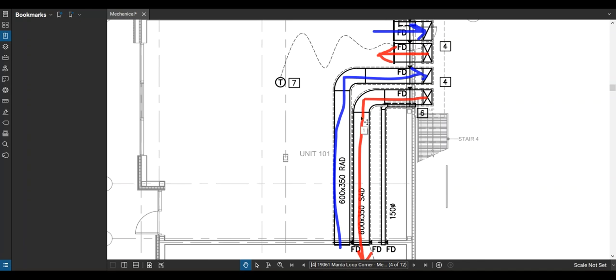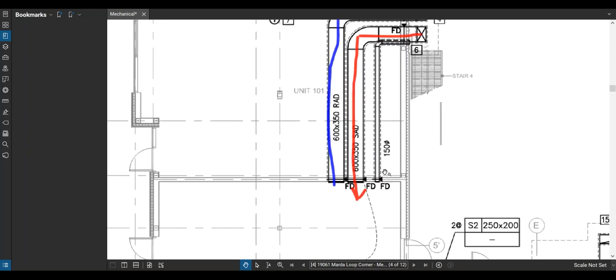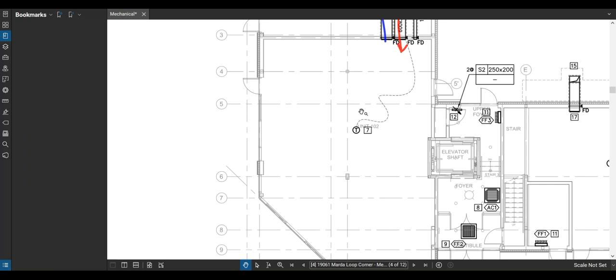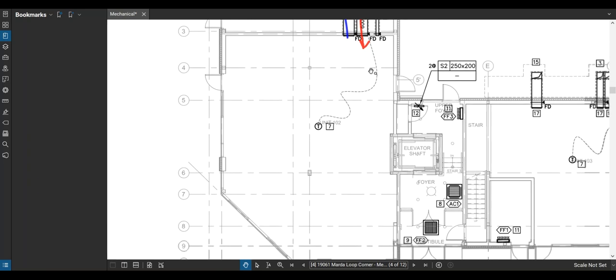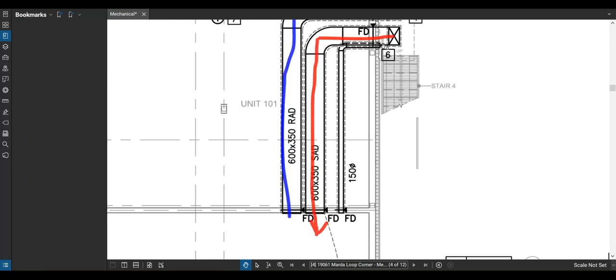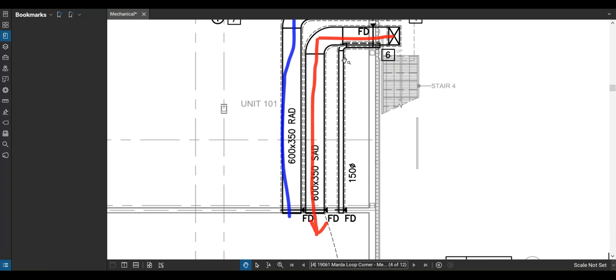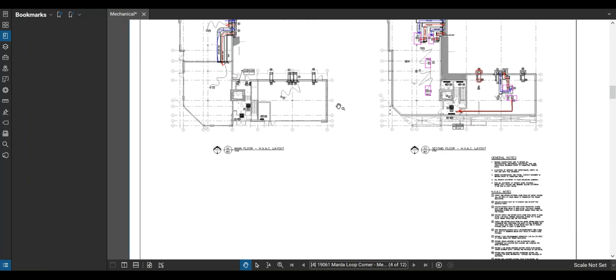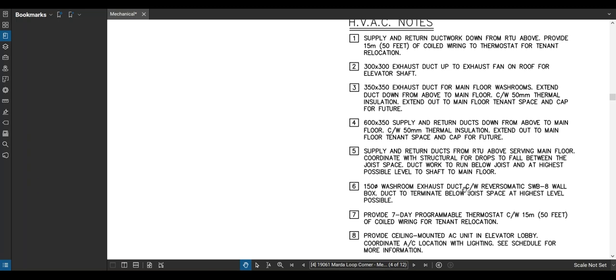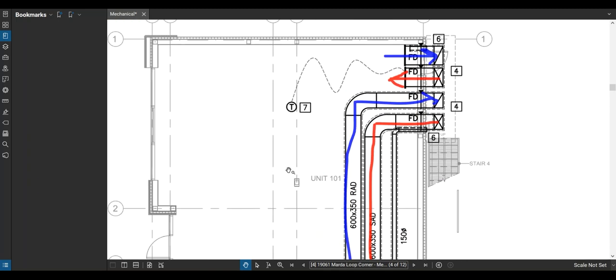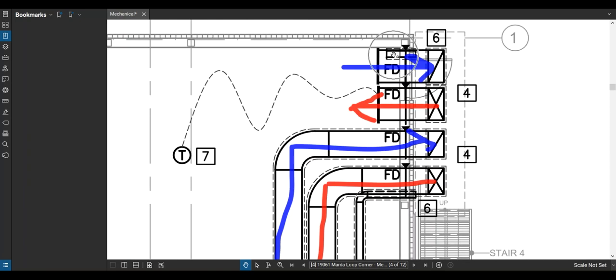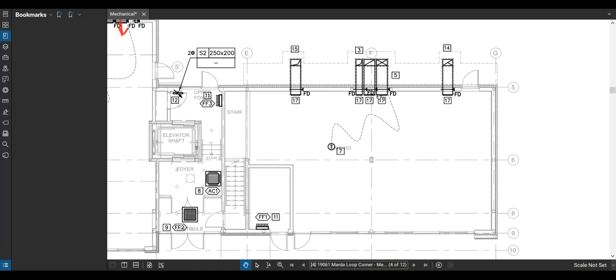This means that this tenant over here is going to have some ducts along the ceiling in their space. There's also a 150 mm diameter exhaust duct, which is an exhaust duct for the future bathroom. The landlord doesn't know where the tenant's going to put their bathroom, but they're going to put rough-ins for them — especially because on the main floor it's going to be hard to exhaust the space. They've run an exhaust duct up through the roof. Reading note 6, it's a 150 diameter washroom exhaust duct. The other space has the same idea.